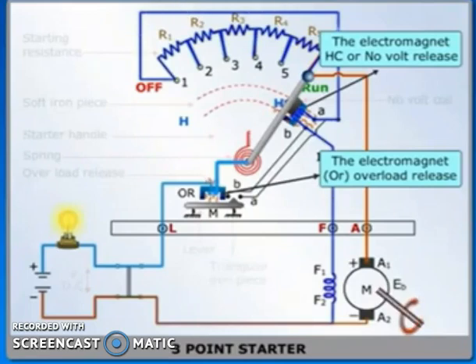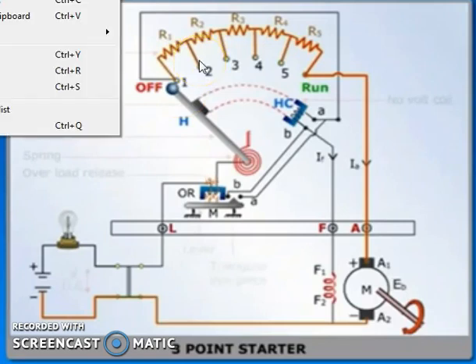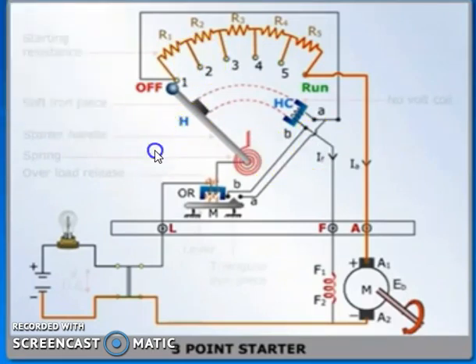Function of the HC or no-volt release coil: In case of power failure, electromagnet HC gets demagnetized, and the spiral spring brings the handle back to its OFF position. Now the circuit is cut. If during power failure the handle fails to return to OFF position, the motor might get damaged.